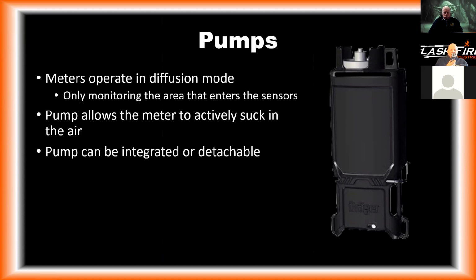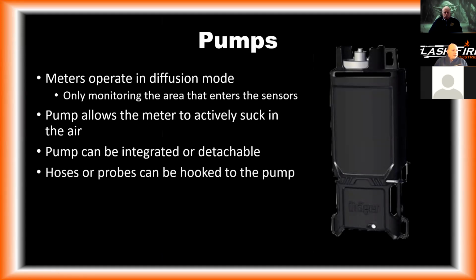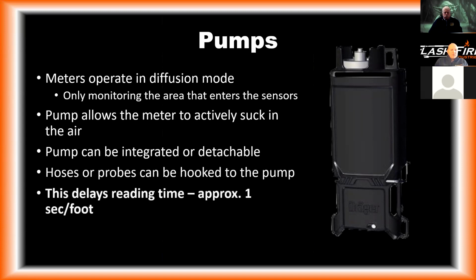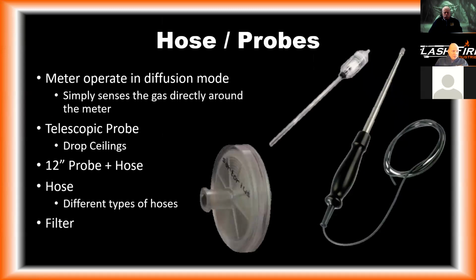For the X-am 2500 you guys have, I forget how many pumps you have, but they're obviously detachable. For the new X-am 8000 that you have, the pump is actually built in. Hoses or probes can be hooked into the pump. The rule of thumb is about a second a foot. So if you have a 20-foot hose on there, it's going to take about 20 seconds for the air to get sucked through the meter.